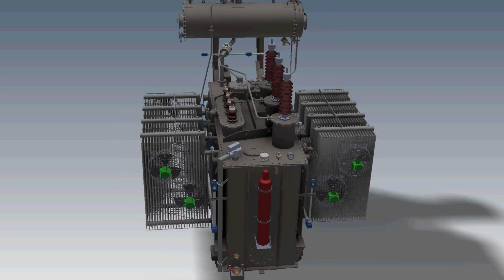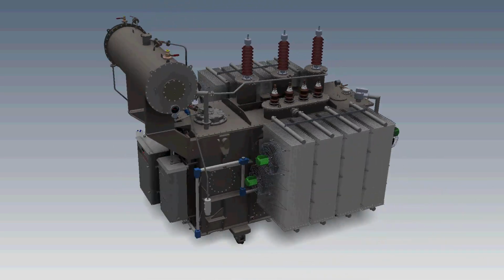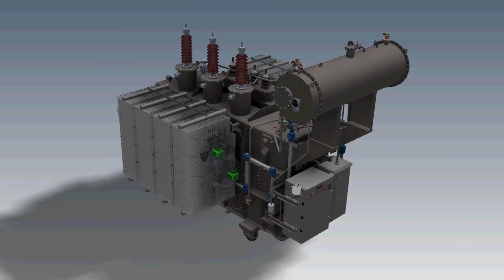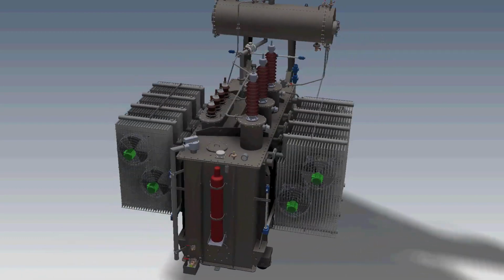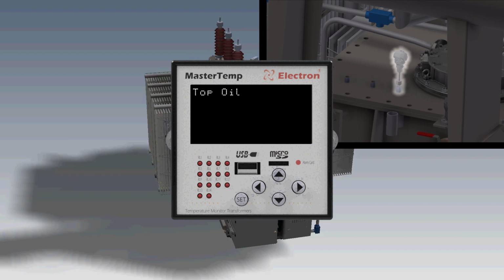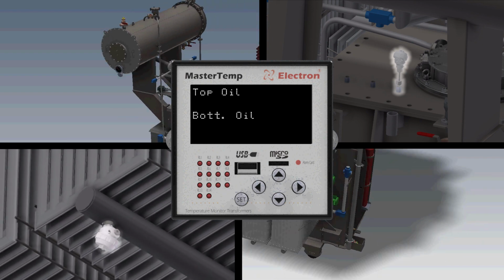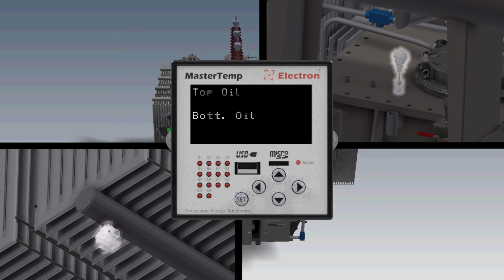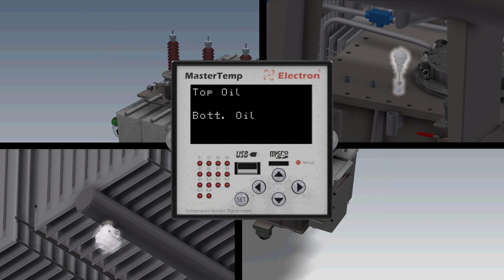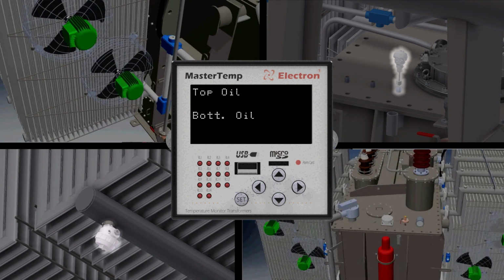Another interesting application is the calculation of refrigeration efficiency. Using two sensors type PT100, one installed at the top of the oil and the other at the bottom of the radiator, data can be monitored that demonstrates the degree of efficiency of the transformer cooling system.